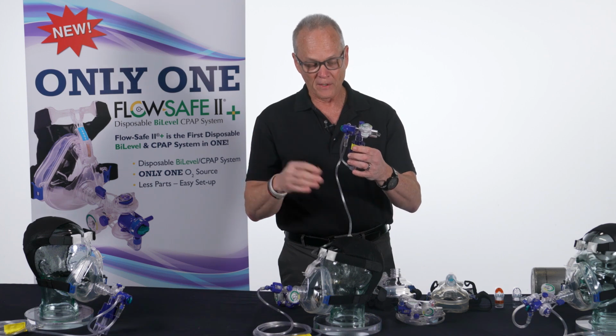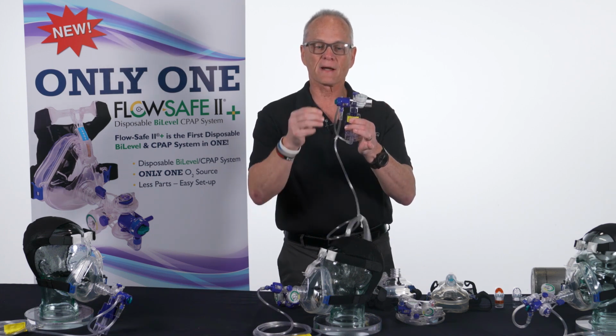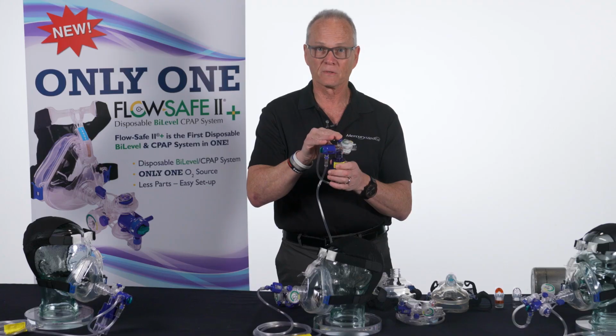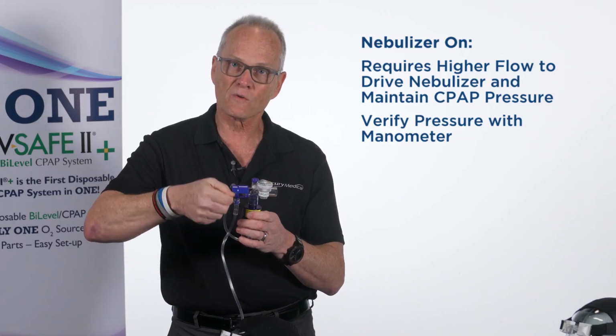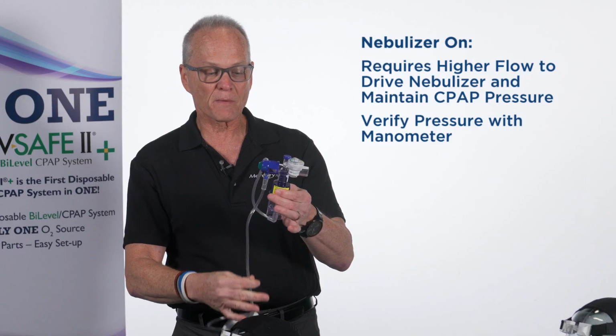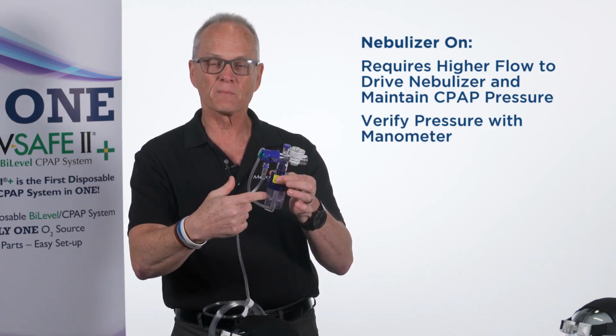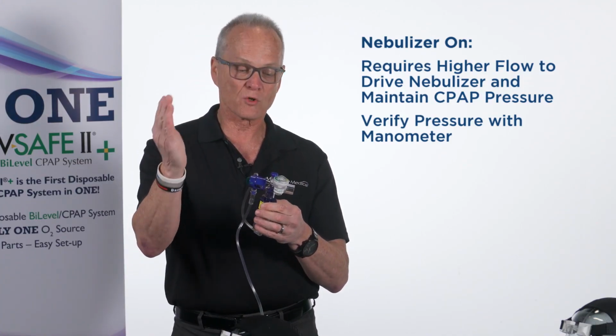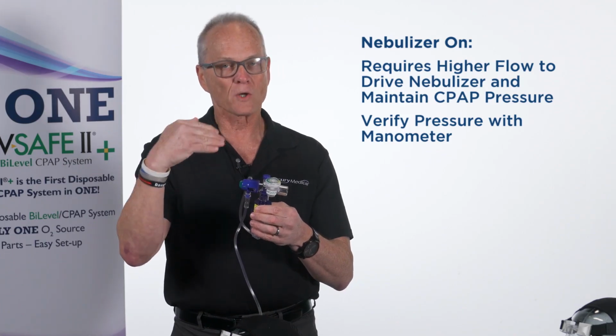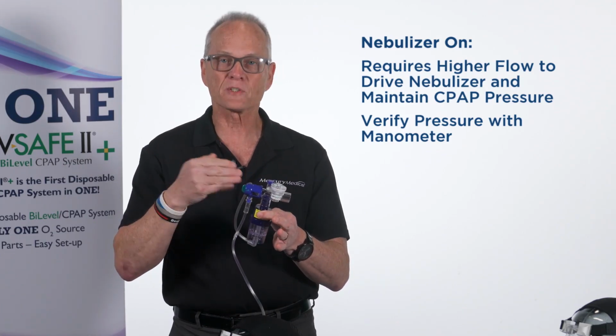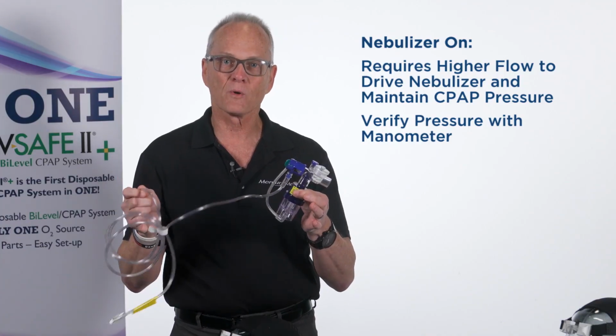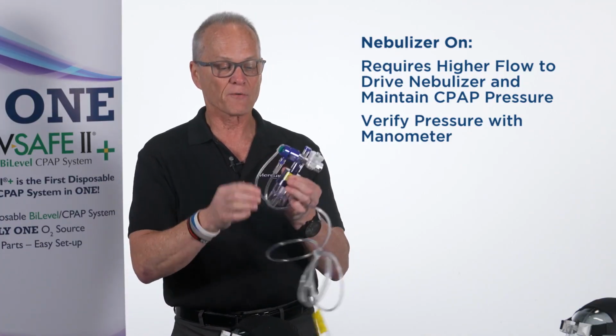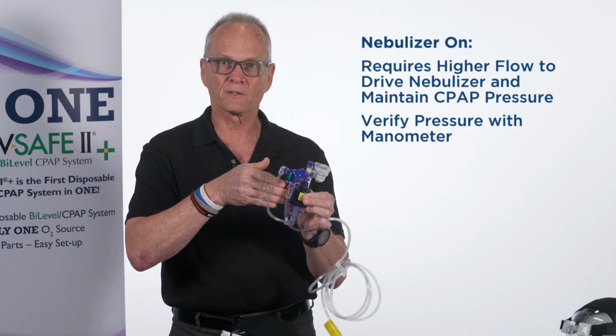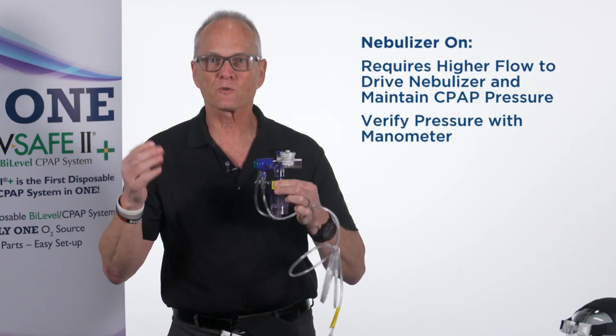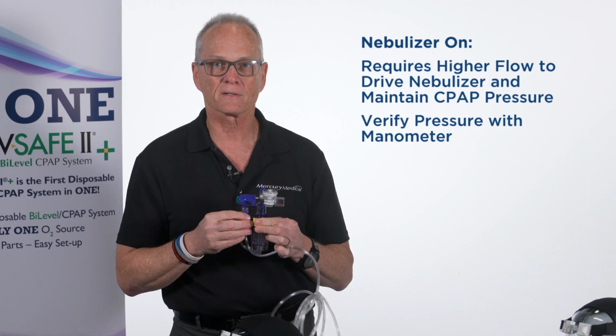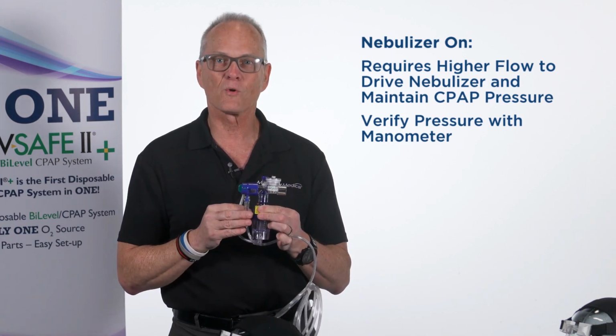Now you have to remember though, if I'm going to put 8 liters in here and I've got it in the off position, this is a FlowSafe 2. But as soon as I turn the nebulizer on, some of my gas flow is being diverted to the nebulizer, so your pressure is going to drop. That's part of the design. To compensate for that, I'm going to have to turn my gas flow up to the device to make up for losing some over to the nebulizer. I've had people say, well, yeah, your pressure drops when I do that. Yes, you're right, that's correct, because we've taken some of the gas flow away.